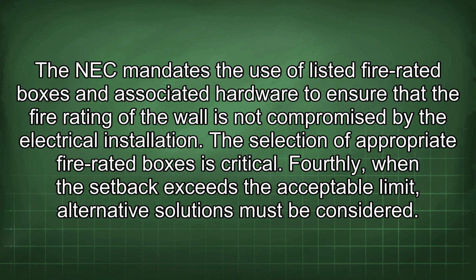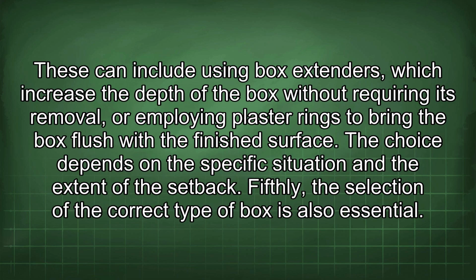Fourthly, when the setback exceeds the acceptable limit, alternative solutions must be considered. These can include using box extenders, which increase the depth of the box without requiring its removal, or employing plaster rings to bring the box flush with the finished surface. The choice depends on the specific situation and the extent of the setback.